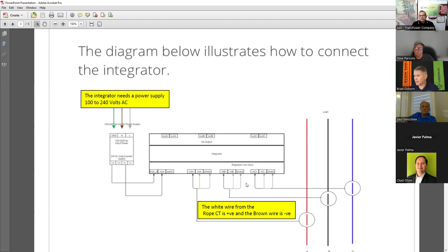Right on, Brian. Did I share another screen? Right now, I'm seeing the diagram that illustrates how to connect the integrator. Yeah. So these are the CTs on the 3 phases. And then you have a brown wire and a white wire coming from each CT at the end. And then there is a shield. It's insulated. So you have positive, negative, shield, positive, negative, shield, positive, negative, shield. Most of the time I see people ignore the shield, which is nothing but a ground wire, which is where the integrator kit is grounded. So you want to remove the static electricity from the shield of that cable insulation.